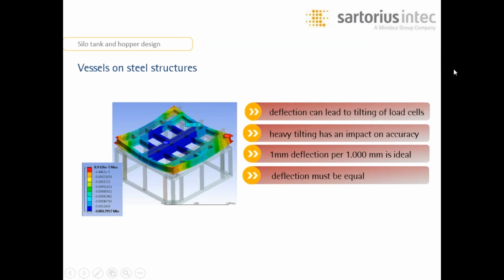Vessels on steel structures. As you can see here, deflection can cause the tilting of load cells. Anytime the load cells tilt, you can have an introduction of an erroneous weight signal. The heavy tilting has an impact on the accuracy. Deflection must be equal on all sides. They're looking for a straight vertical load.